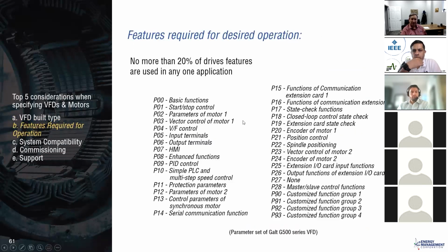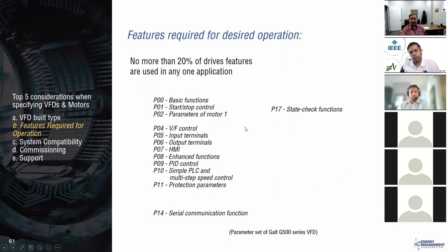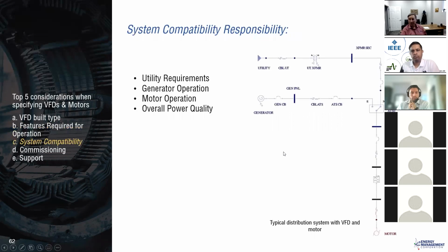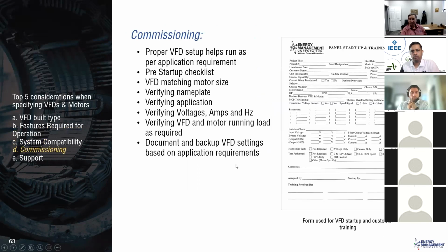Also, when you specify the features in a VFD, you've got software and hardware features. You've got the number of digital inputs or analog outputs or whatever. You're probably aware that there's almost no one that uses even 20% of all the parameters. There's over 500 parameters in most drives nowadays. So just getting to the right ones is necessary. And also maintaining that those parameters are kept there from a long-term standpoint is necessary. Compatibility, I think we talked about most of all those issues. Commissioning is obviously an important part of all projects, that you document that. There are specifications where they actually ask us to measure.